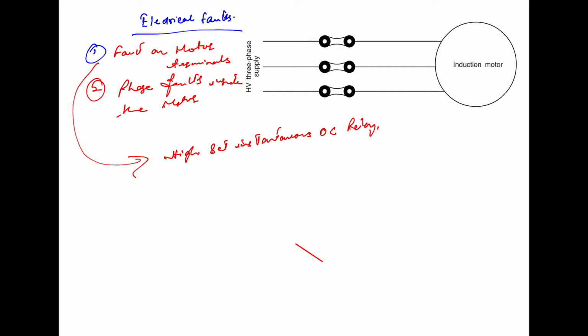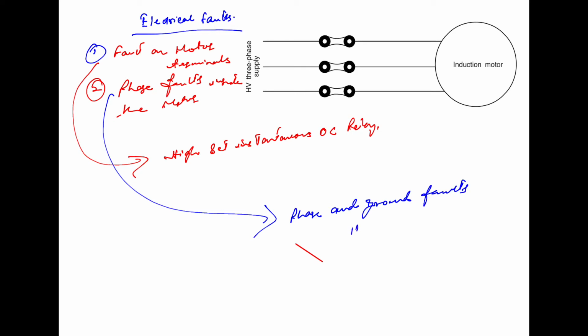Now the second is the phase fault inside the motor. The protection against the phase fault as well as the ground fault can be provided either by using fuses or overcurrent relay, depending upon the voltage rating.